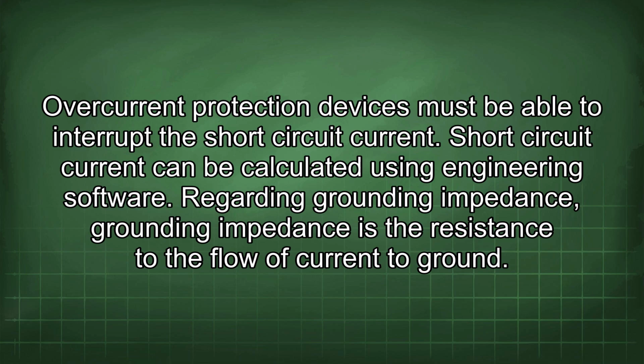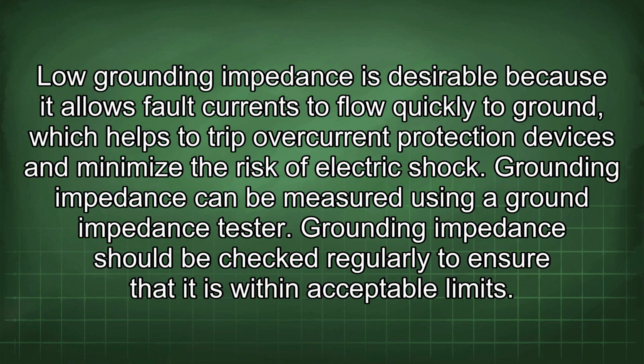Regarding grounding impedance, it is the resistance to the flow of current to ground. Low grounding impedance is desirable because it allows fault currents to flow quickly to ground, which helps to trip overcurrent protection devices and minimize the risk of electric shock. Grounding impedance can be measured using a ground impedance tester. Grounding impedance should be checked regularly to ensure that it is within acceptable limits.